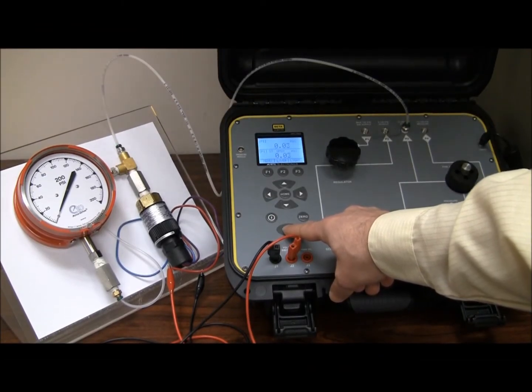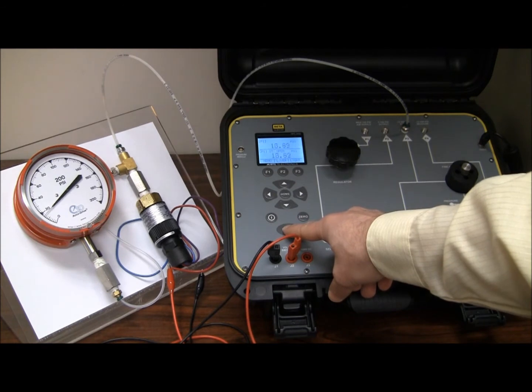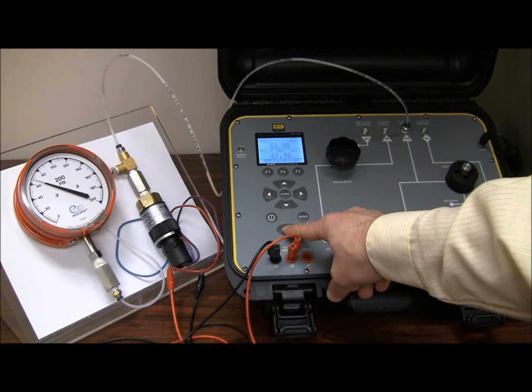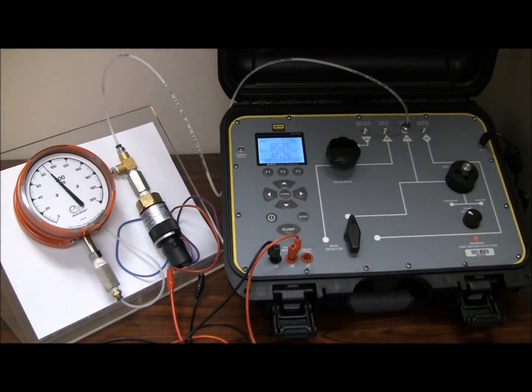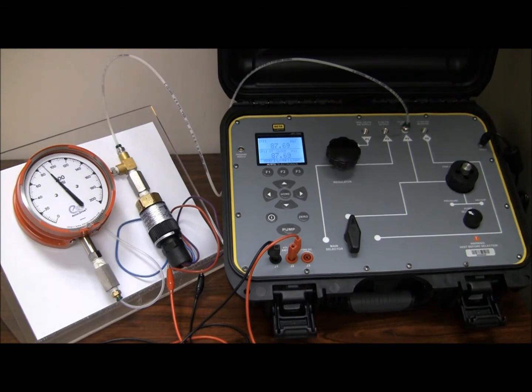Let's take a closer look and perform a quick pressure switch test. I have a 125 psi pressure switch that is teed in to a 200 psi mechanical gauge so you can get a better feel of how things work.